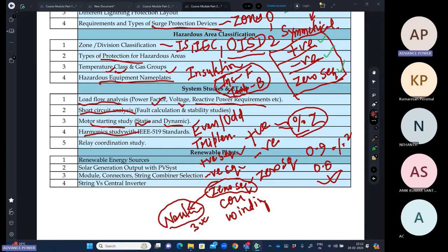Then we'll do the relay coordination study. So in relay coordination, we'll prepare a single line diagram and go from motor level to generator level. We'll do the coordination. We'll prepare a curve and we'll see how the time gradation and current gradation we are using for coordinating the different relays.